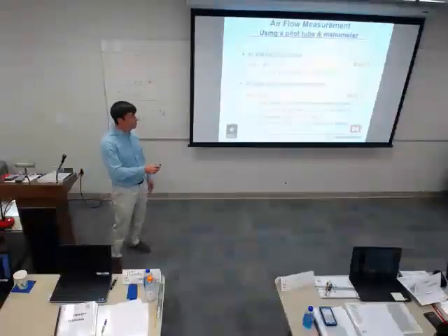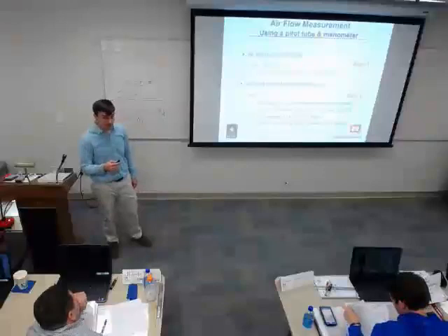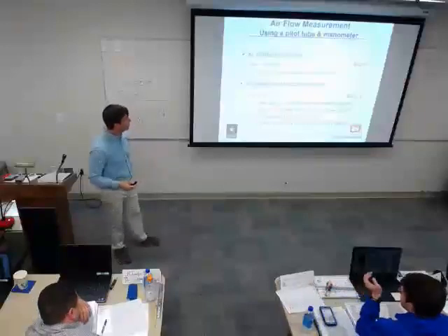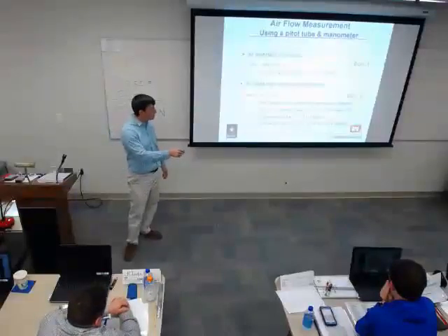All right, going back to this equation, and you are going to need to do this tomorrow in your lab. I keep talking about it. So remember, for standard conditions, 4,005 times the square root of velocity pressure. And where do we get velocity pressure from? Traverse, right? And if I'm at other than standard conditions, I have to find my density at that point and do a correction.